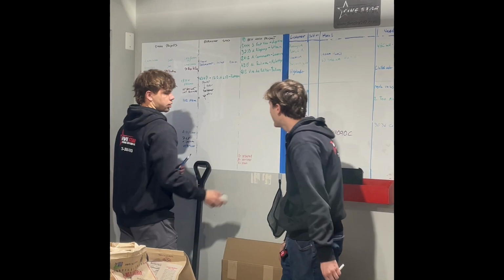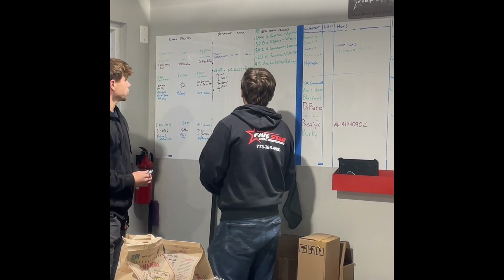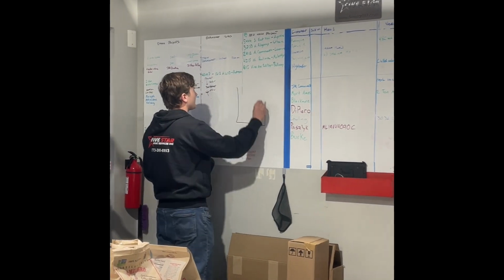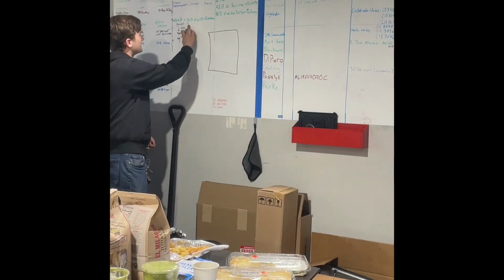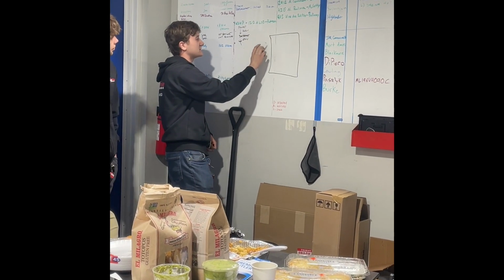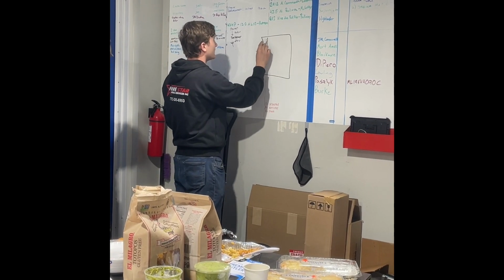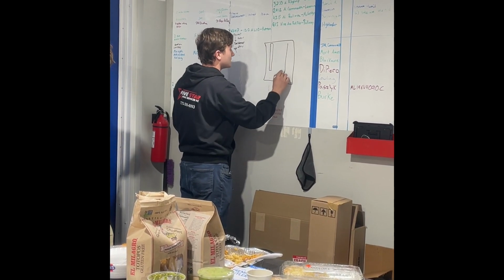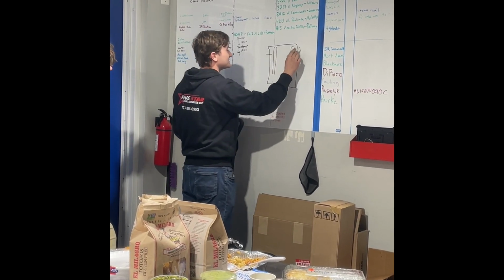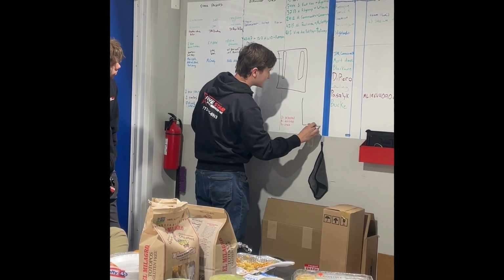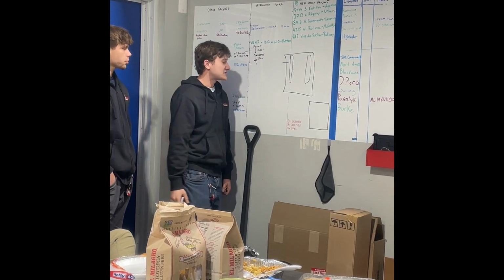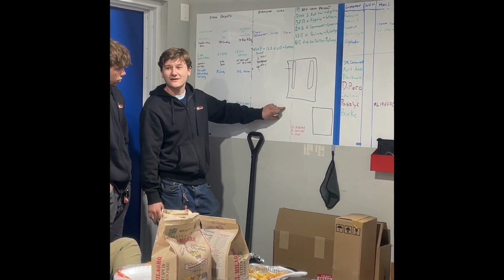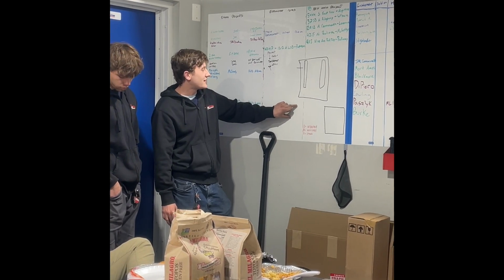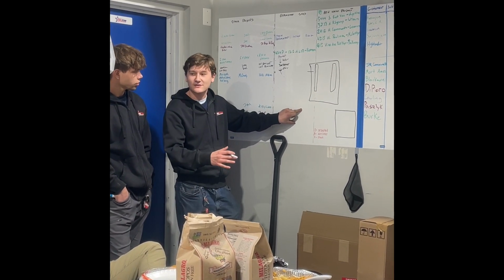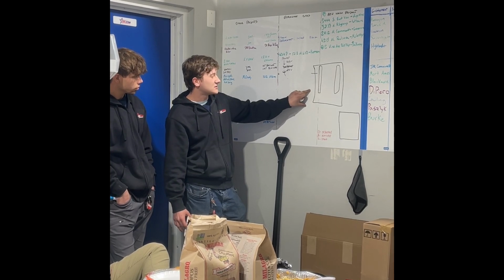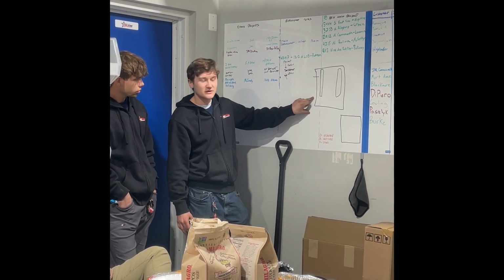I can start with the wiring. Okay, so here we go. We started with sending power from the power source through our transformer to the zone control board. Here's a drawing. And then we had our Unico control board connected to our zone control board. Basically how this works is there was a thermostat in the master bedroom of the house, and we also have a thermostat in the other side of the house. So we wanted to be able to have two zones. We have 3 dampers, only 2 zones though.